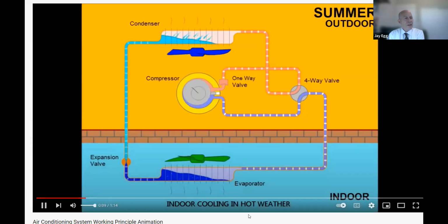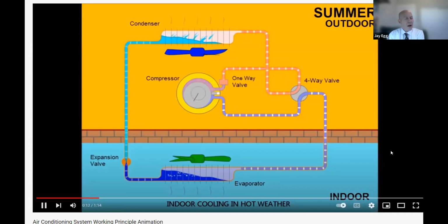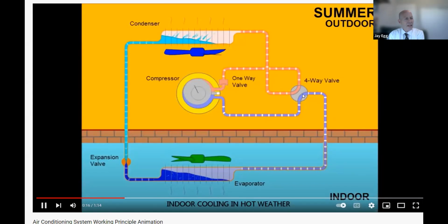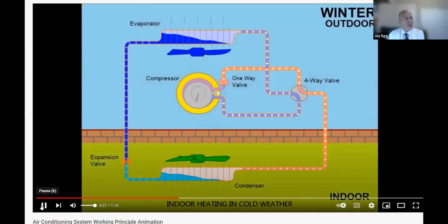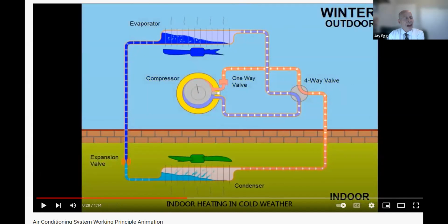So as you look at the summer or cooling effect, you'll see that this has, for air conditioning and heating, a special component called a four-way valve, which allows the heat pump to switch. And you're watching it right now. Look at it switch from summer cooling to winter heating. Now it's cold outside. What did it do? It switched the condenser from the outside to the inside. Remember, I said the condenser coil is the coil that gives off heat. So now it can heat indoors. And that's how it operates.